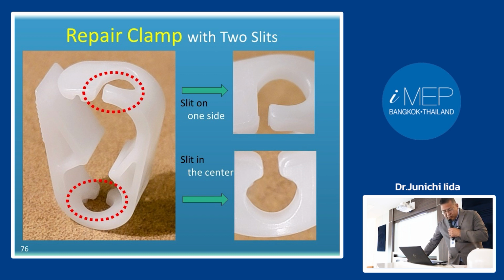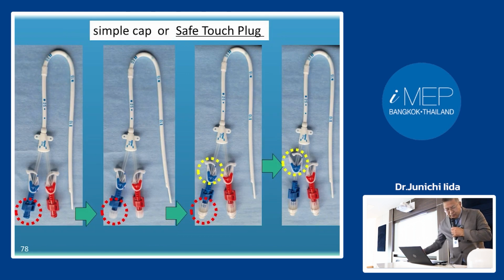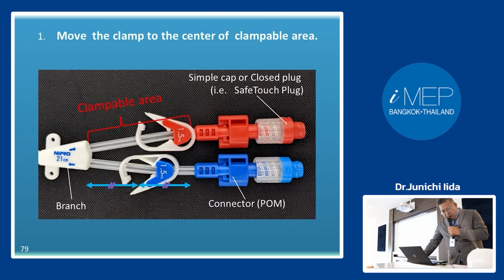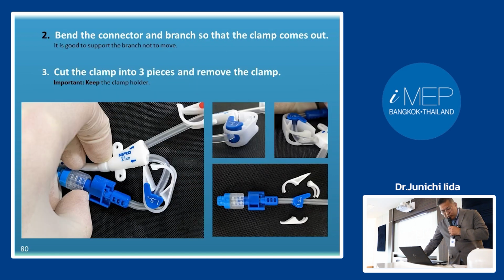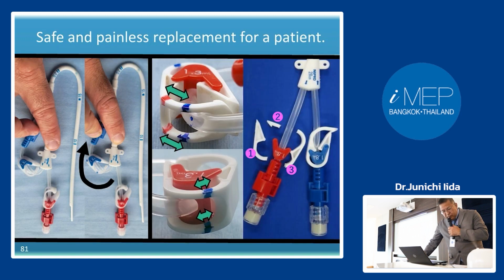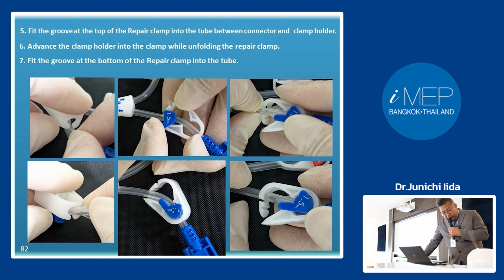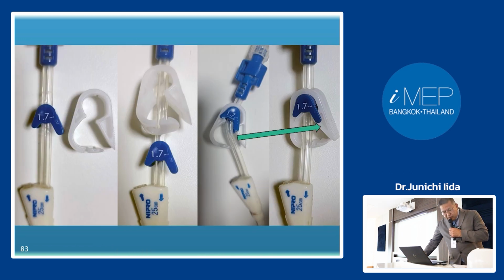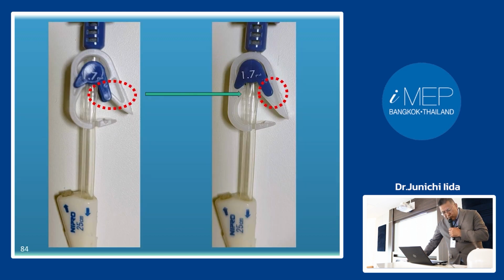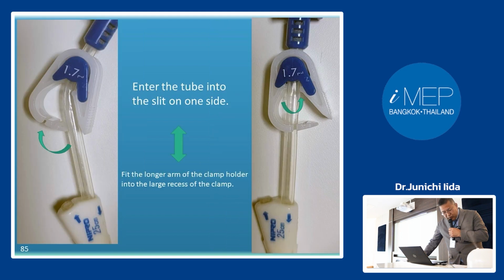There are only three points, and it is easy to repair. First, move the clamp to near the center of the line. Move the clamp to the center of the clampable area. Pinch the connector branch so that the clamp is exposed. Cut the three parts with nippers and pass the finger through, squashing the branch through the central slit so that it is at the distal position of the clamp holder. We fit the longer arm of the clamp holder into the large recess of the clamp. Finally, insert the branch pipe crushed with our fingers into the slit.